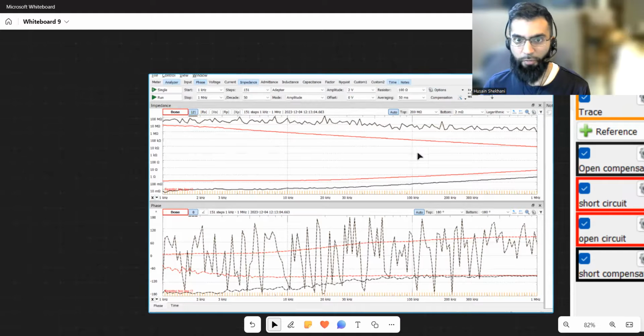This top red line is open circuit with compensation on. This bottom line is short circuit with compensation on, and this one is with compensation off. When you turn on compensation, you get higher open circuit impedance and lower short circuit impedance.